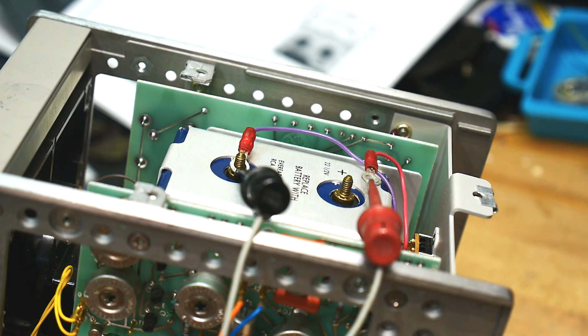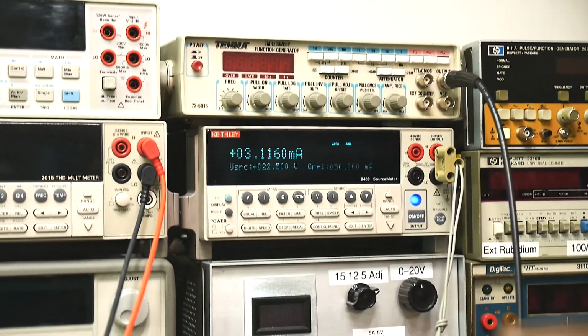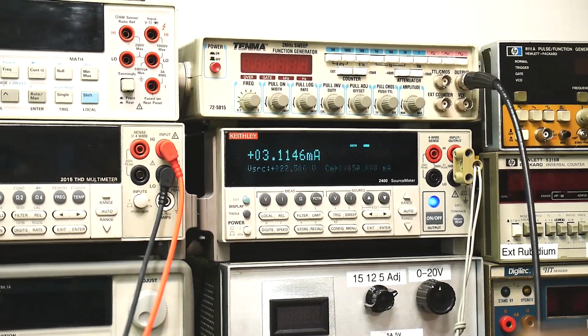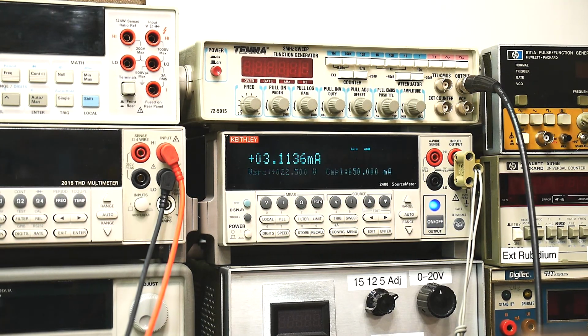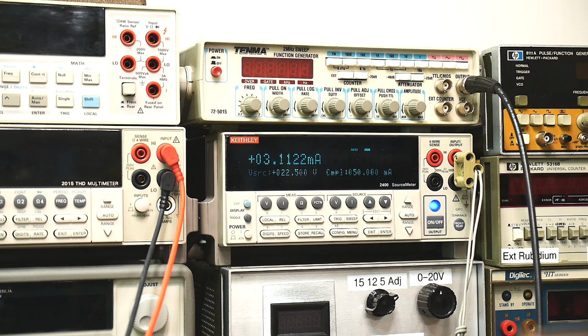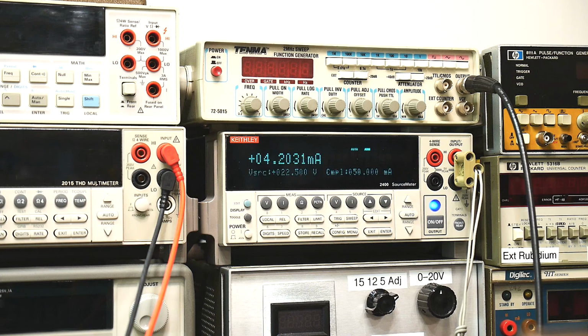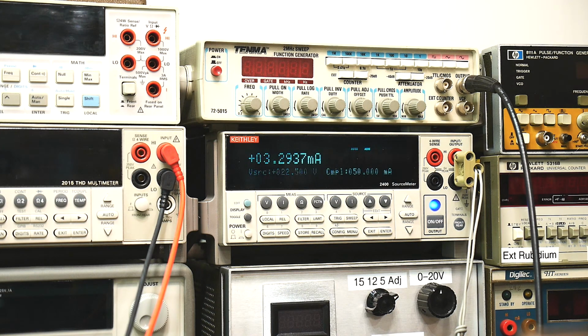Now on the front panel, I'm going to switch it to DC volts. Oh, there we go. So we're measuring 3.1 milliamps for DC volts, and it should be irrespective of range. I'm going to change the ranges. Yeah, it's always 3.1. And if I hit AC volts, it's around 4 milliamps to run the meter. And then ohms, 4, 3, 12. So on the lowest, on the 10 ohm scale, we are going to draw 12.5 milliamps. But otherwise, it's always around 3 or 4. So the whole thing operates at 3 or 4 milliamps all the time.